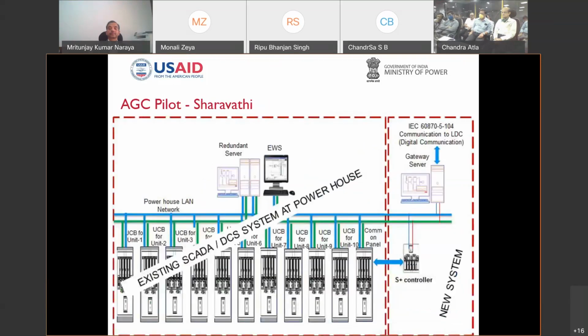We all learned automatic generation control in our undergraduate program, but it was essential to gain real experience over the years, seeing how primary control and free governing mode operate in India alongside AGC. At the Sharavati pilot, the existing SCADA system was there, and with the vendor ABB, a substation controller was supplied along with various other hardware and gateway servers, enabling us to get the signal from the KPTCL LDC and set the appropriate signal.